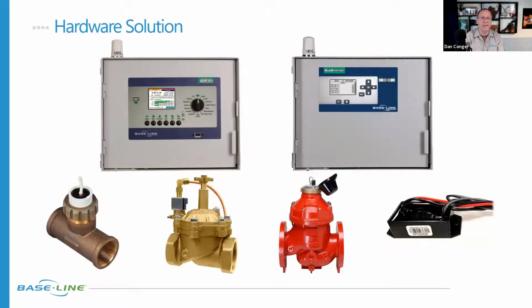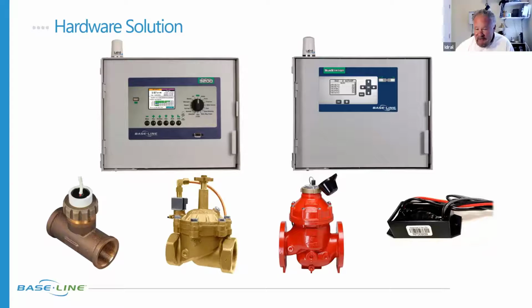As the water level changes in inches, the different event bicoders get a signal that tells either the wells to kick on or to kick off. One of them tells the schedule to stop the entire system, except for the wells. They all have a kill switch, if you will, a master kill. They can't go below a certain number of inches.